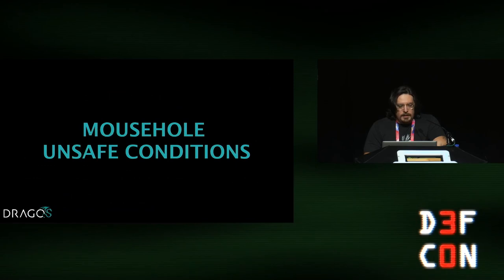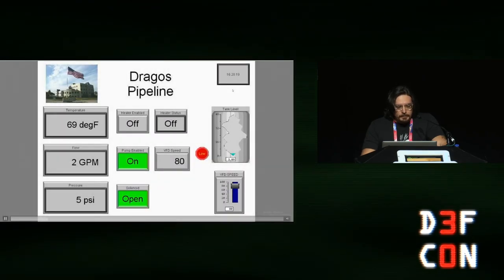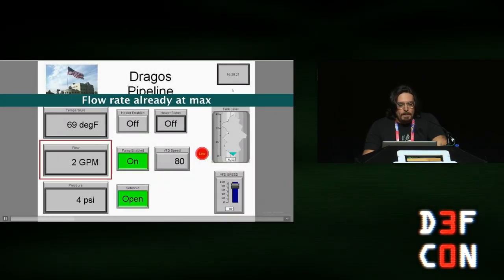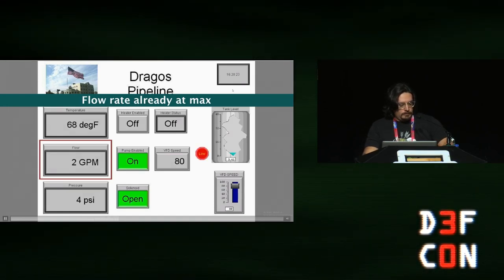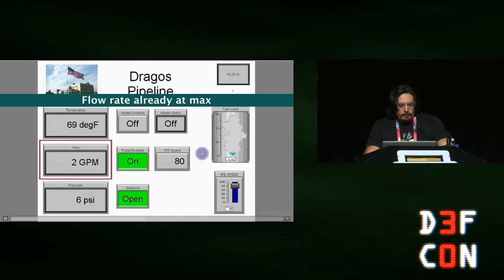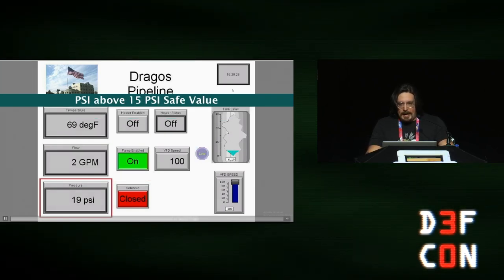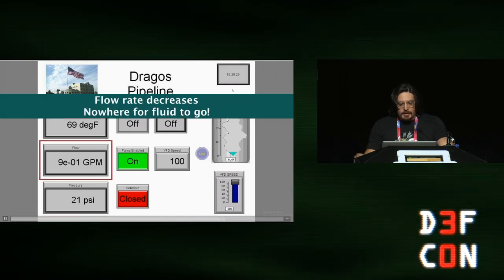Here's what it looks like on the HMI screen when you execute Mousehole on the pipeline. The flow speed is already at max. The solenoid valve closes, pressure goes up — already past the limit. The flow rate starts to decrease — not because the pump is off, but because the pipe is full and there's nowhere for the fluid to go. The pump is trying to get water into the pipe but the pressure is too high. It just can't fit.